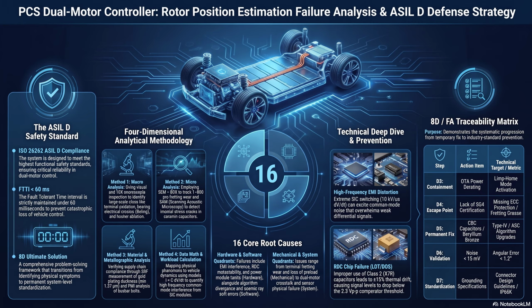The rapidly switching stator windings capacitively couple to the rotor iron, which induces a high-frequency common mode voltage on the spinning motor shaft. Okay, so the shaft gets electrified. Right. Now, the shaft rests on steel bearings, but it is floating on a microscopic hydrodynamic film of lubricating oil. And oil is an excellent dielectric. It's an insulator. It is, up to a point. We measure shaft voltages hitting anywhere from 70 to 370 volts.